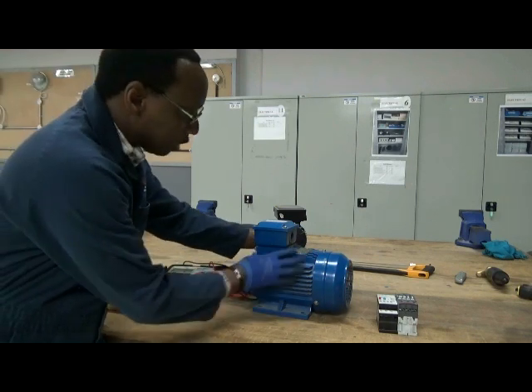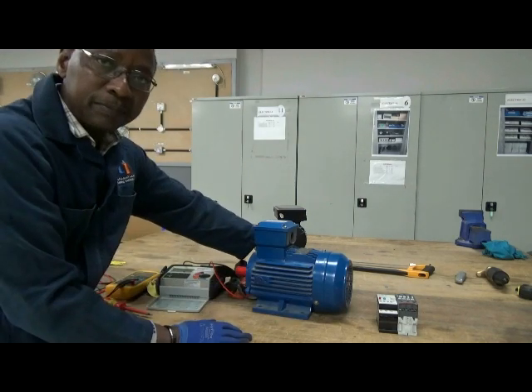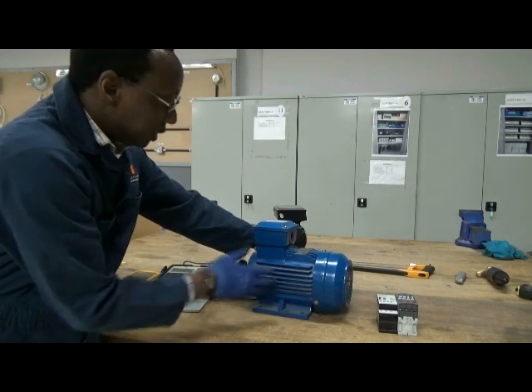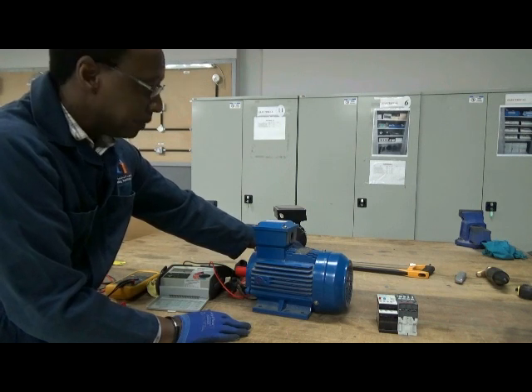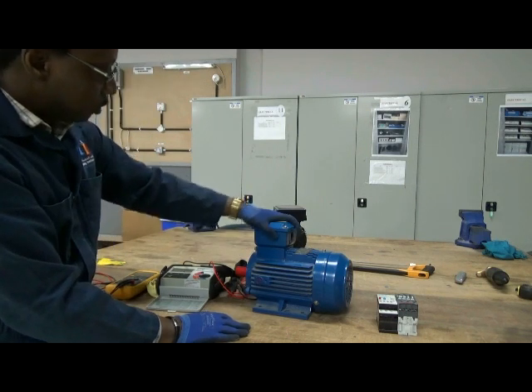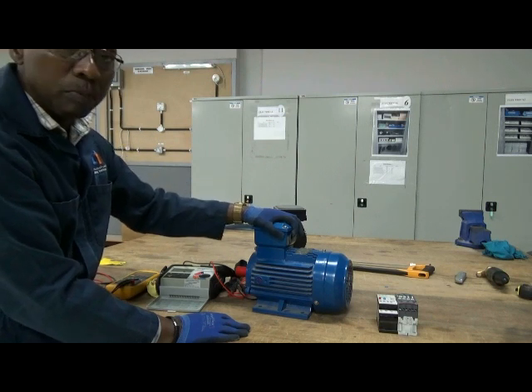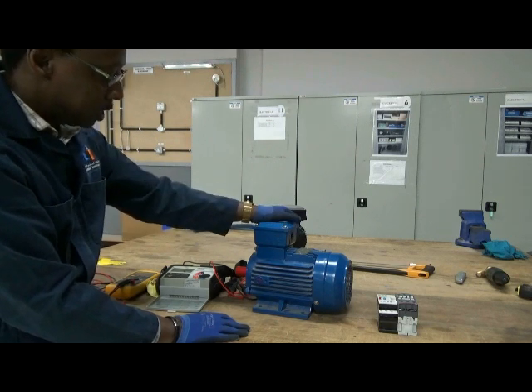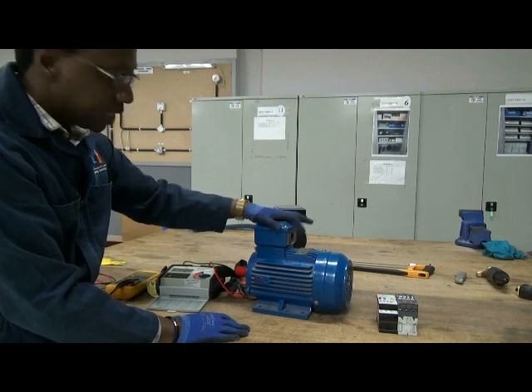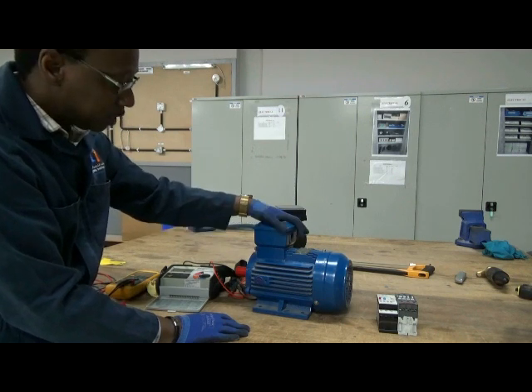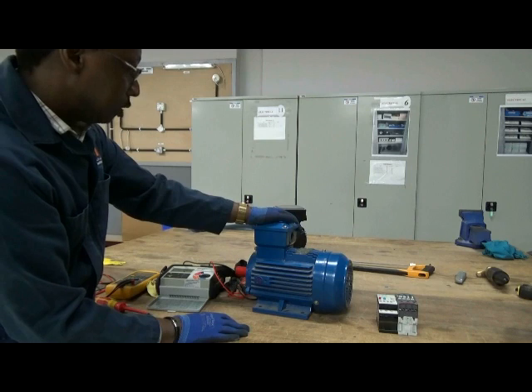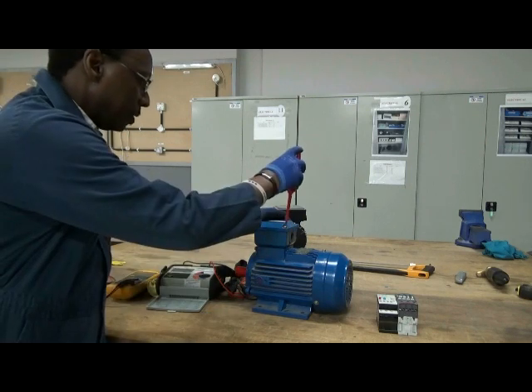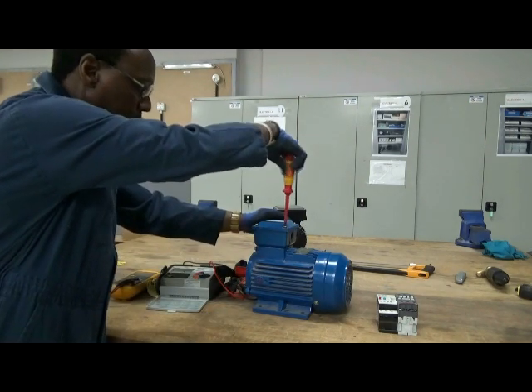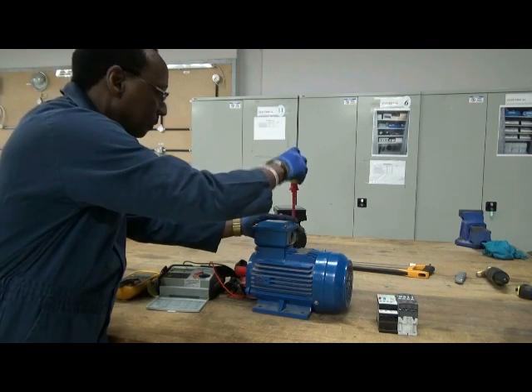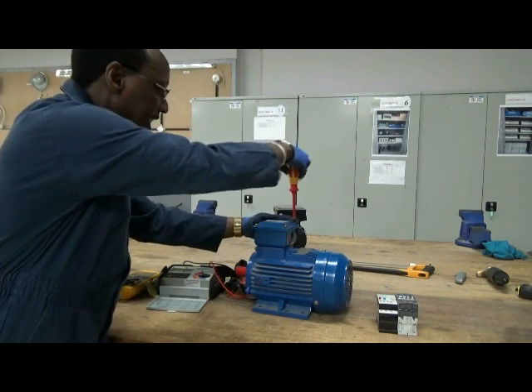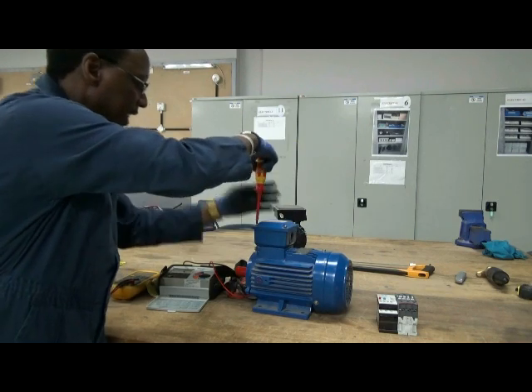So inside, around the stator, we've got stator windings that are wound in there, and we have a terminal junction or a terminal box right at the top where we make our connections, where we connect our three-phase supplies so that the machine can run. So what I'm going to do right at the moment is open up the junction terminal box, so that we can start testing the windings that are inside.